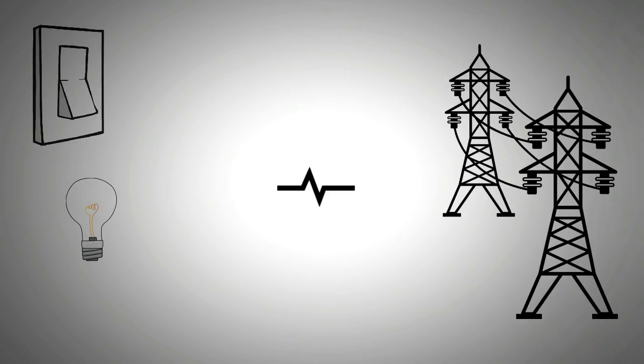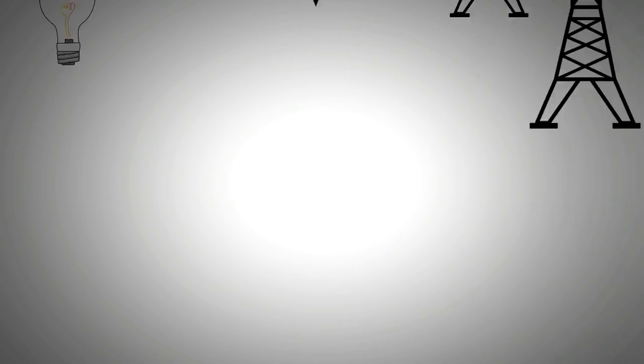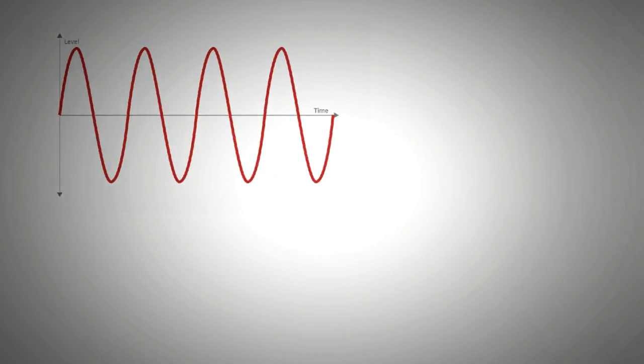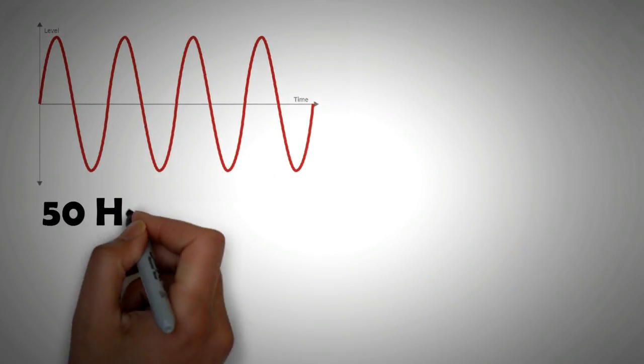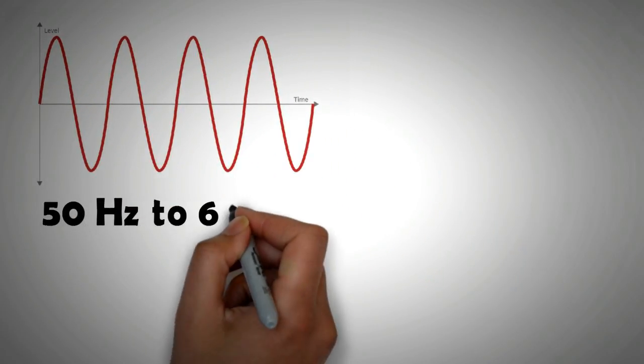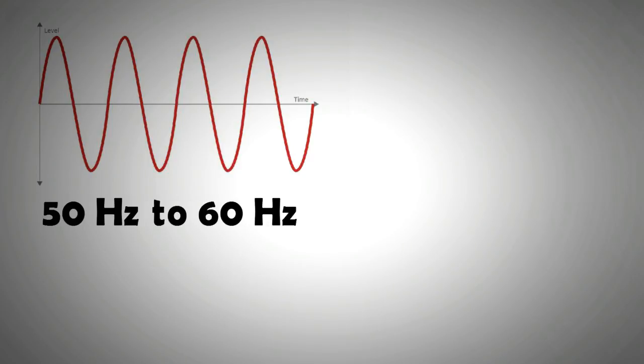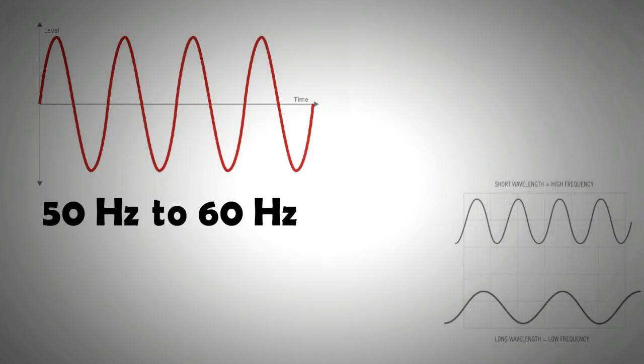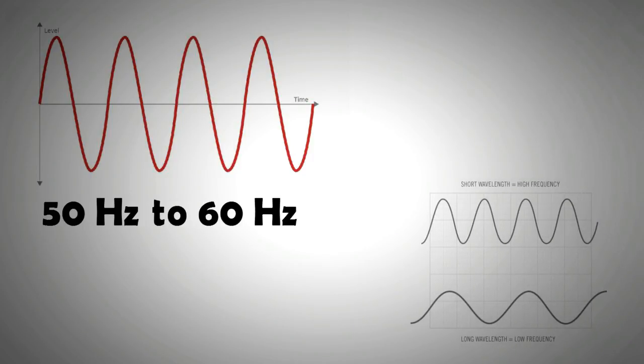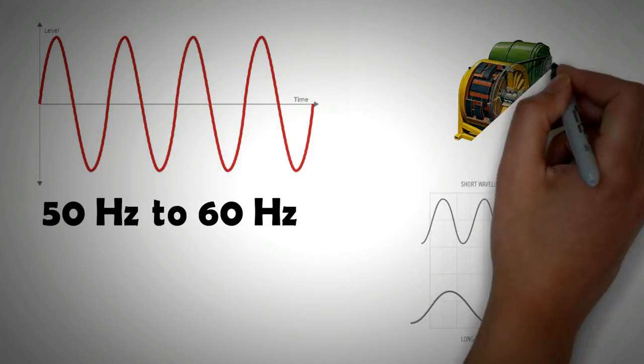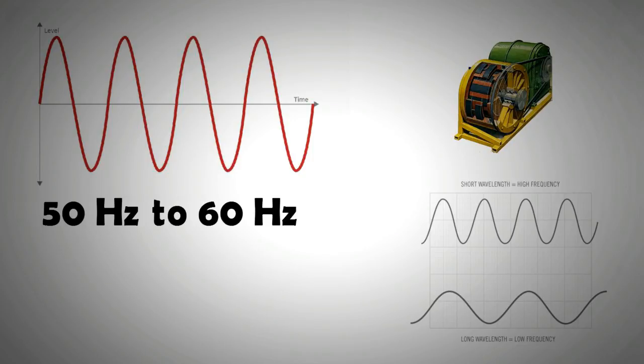Remember, we get our power at a certain frequency that could be 50 Hertz or 60 Hertz, depending upon what the standard and utility infrastructure is in your country. When there is demand and appliances are being switched on, the grid frequency drops. On the other hand, when there is more power in the grid being pushed into it by the generation side and there is less energy being consumed by the end users, for example in the night when a lot of lights are being turned off, then the grid frequency goes up.